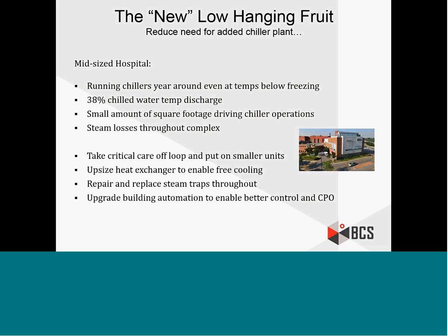They're another case where they'd moved away from a heat exchanger and economizer because they felt the building load was too high for the heat exchanger to handle. So taking the critical care units off of the loop and putting in smaller dedicated units significantly decreases the load. That will let them run chilled water temps at a higher level and will let us put in a heat exchanger for free cooling. Those things alone will drive significant savings.